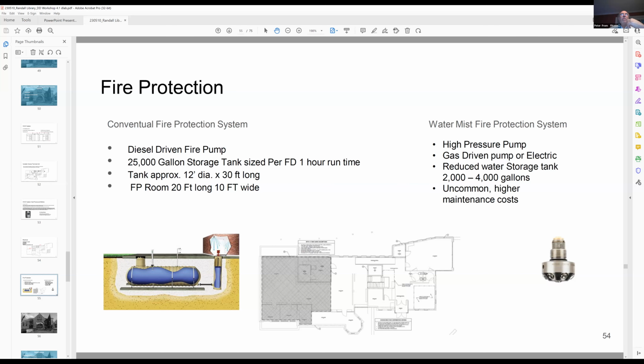This is all NFPA compliant. There are special guidelines for it, but it's uncommon in these types of facilities due to cost. Because if you have a water main and we can do a tie-in, then this doesn't make sense at all for this application. But if you compare a $500,000 cost for the cistern, the fire pump, and everything else that goes along with that, this system is certainly an option to deal with, because we believe the cost would be at or slightly less than that $500,000.